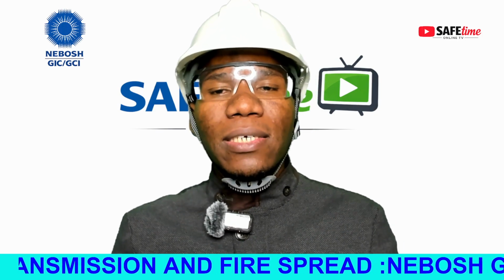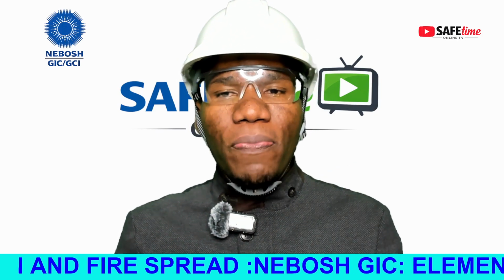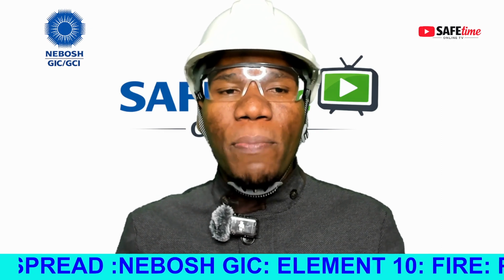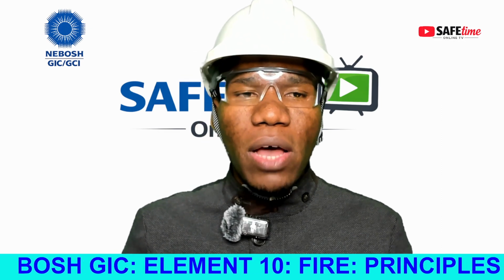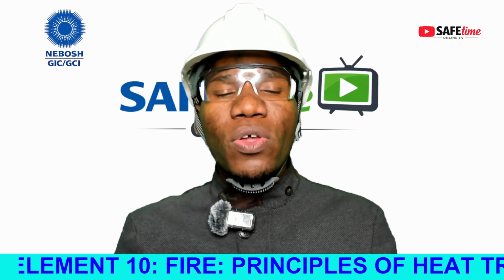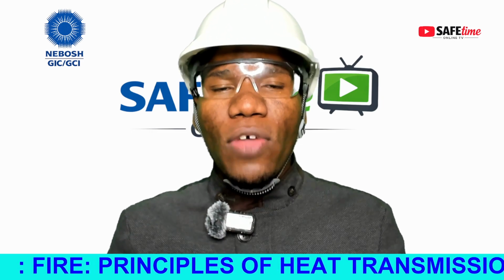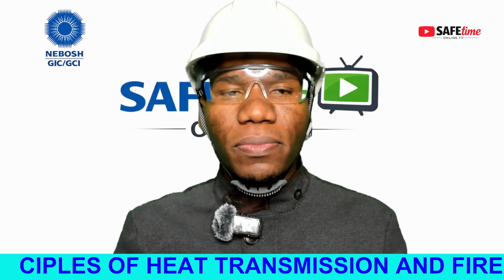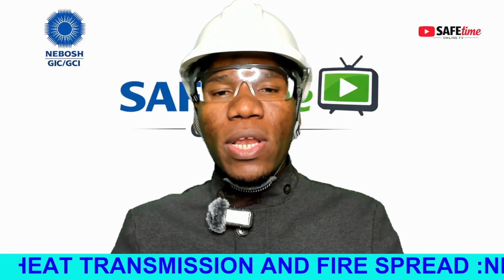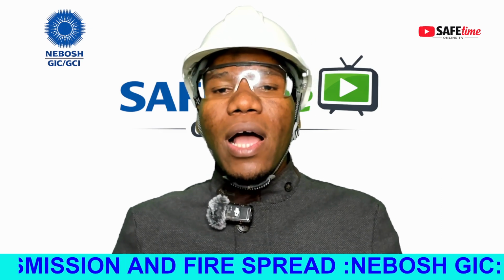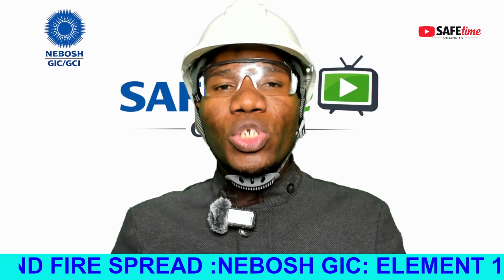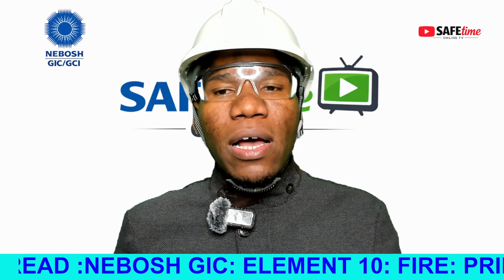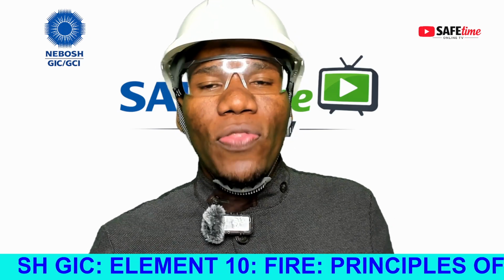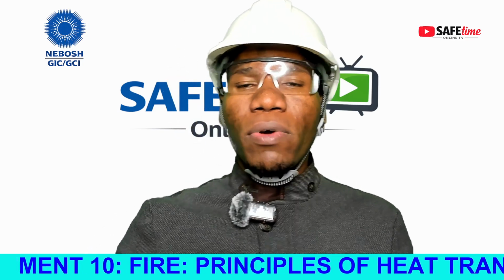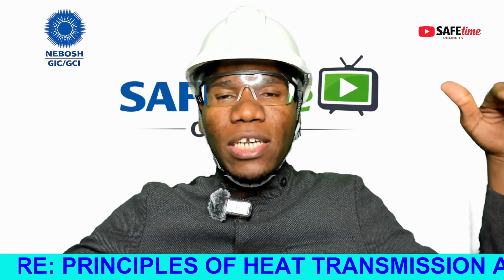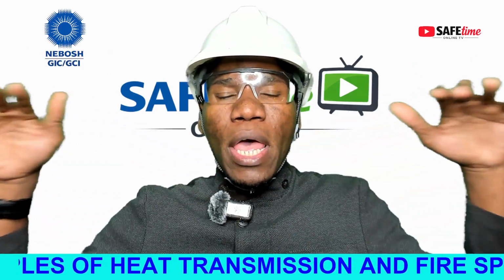So convection is the principle where the hot air rises up and the cold air sinks down. Hot gases generated by the fire rise straight up from the fire. Now, when this happens inside a building, these hot gases will hit the ceiling and then spread out to form a layer underneath. So the hot air, when it rises up, spreads out in that particular room or building.